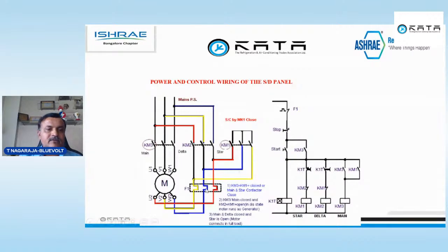The overload will always be in the phase current. See, whenever you measure here, this mains input will be a line current. That means the full load of the motor current. Whenever you are measuring the 6 points, it is a phase current.